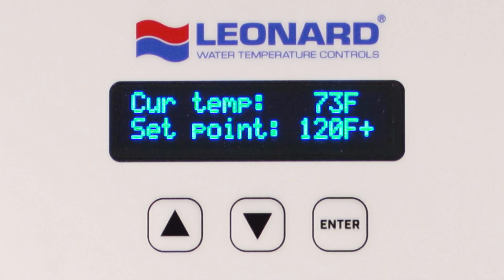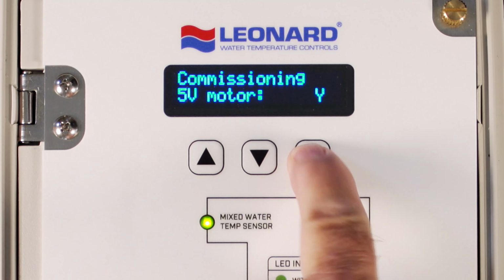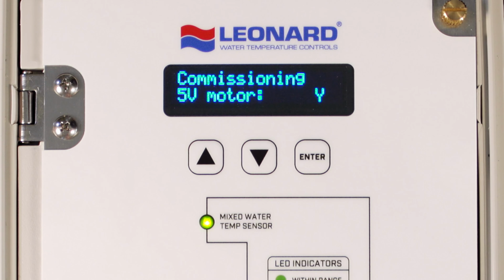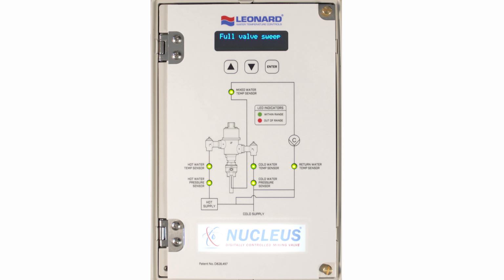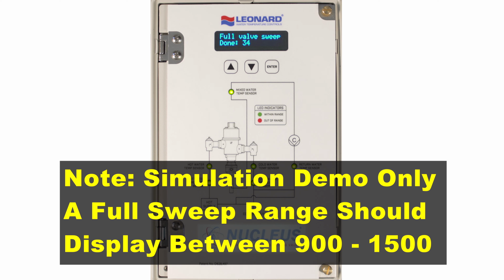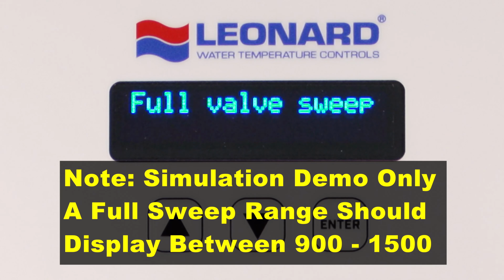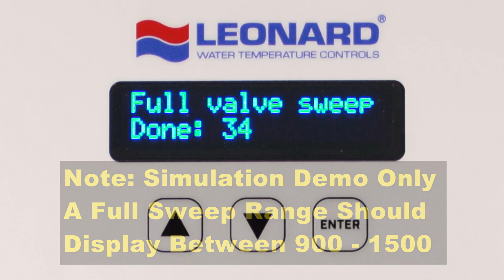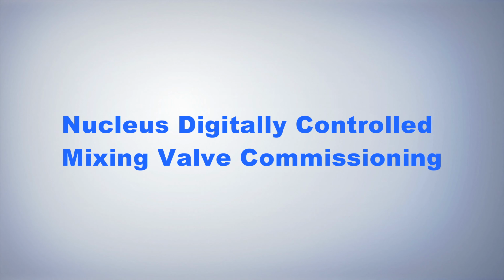The controller uses a 2-line 16-character LED digital display screen which serves as the user interface by utilizing a simple 3-button keypad interface. Up for back, down for forward, and enter for selection. On initial power up, the valve will go through a full sweep function which moves the motor its full travel, end to end of hot and cold ports of the valve body. This process assigns a numerical value to the distance traveled by the motor in steps that will be used in future comparisons to indicate if there is a potential maintenance problem or internal mechanical issue with the components of the valve. Nucleus digitally controlled mixing valve commissioning.